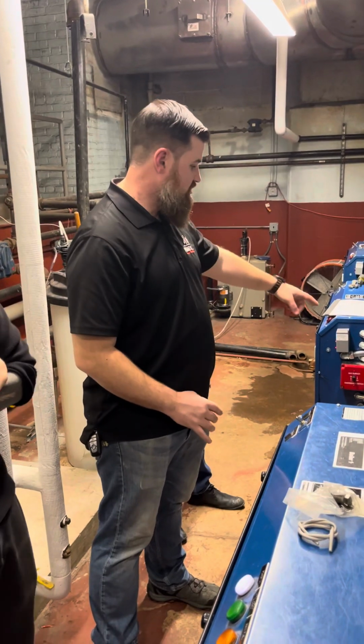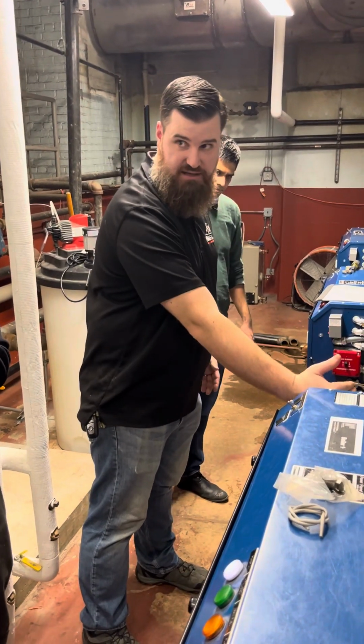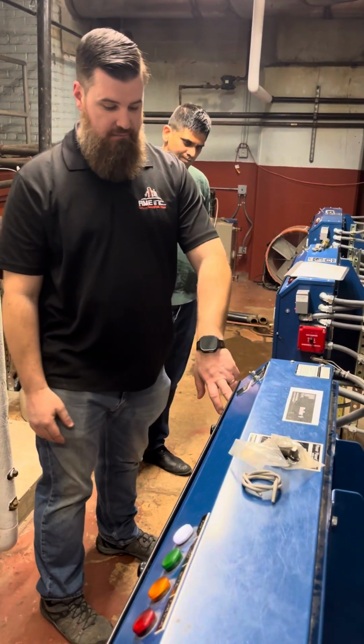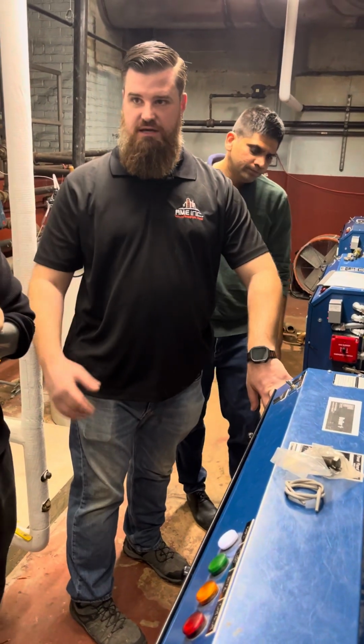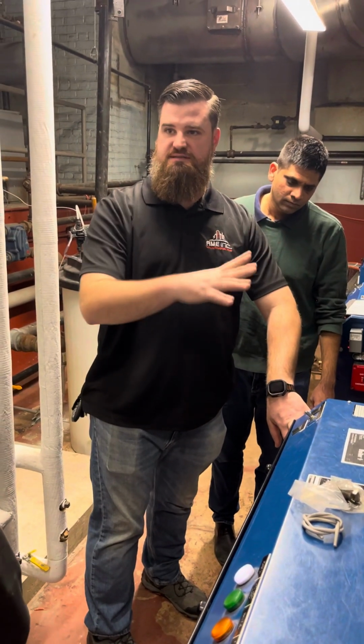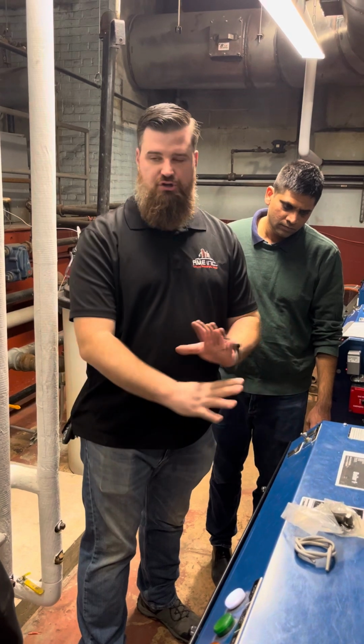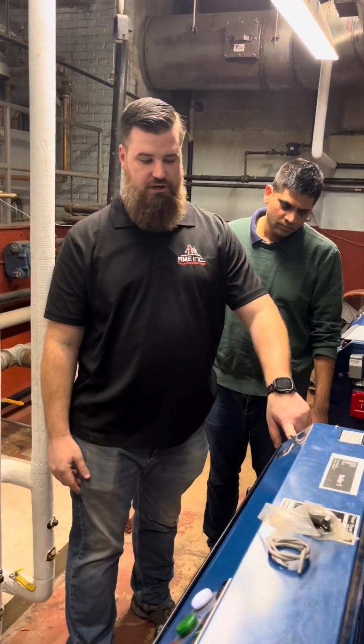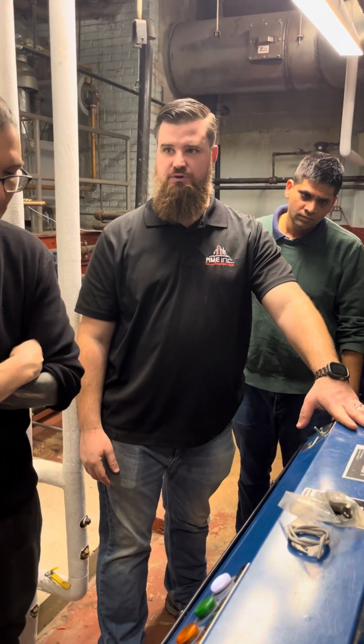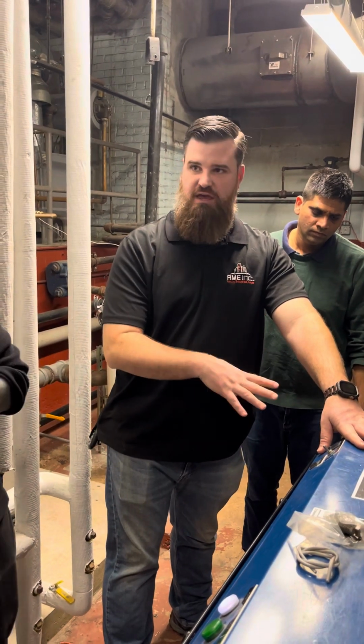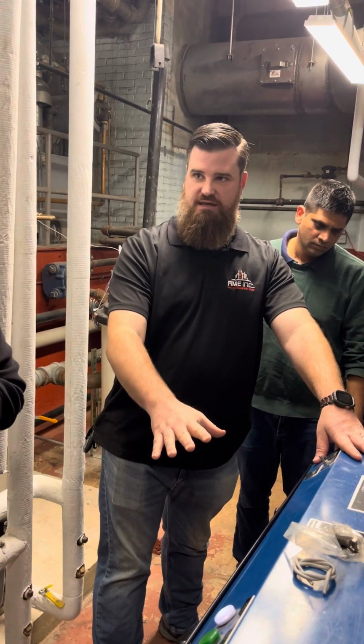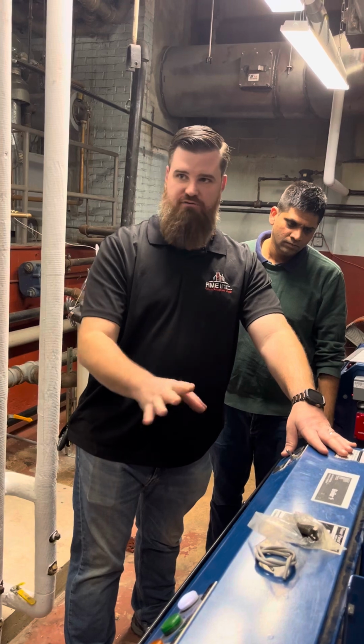Each boiler, they're just on the same side with the power disconnect, okay? Understood, yep. So keep in mind, in auto position, it's going to take whatever command the BMS is sending it. If you put it in open, you're shutting the boiler down, and if you put it in closed, it just bypasses what the BMS is sending and sends the command into this. And then the boiler is going to operate off of whatever settings it has.